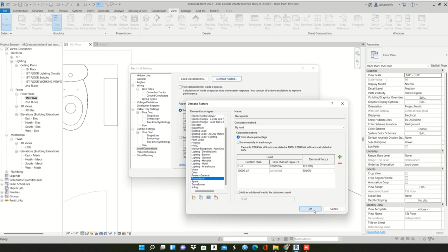Let's assume I'm doing this because we are going to make pizzas, and we're going to use these big machines that consume a lot of energy. I'll hit OK, go back to my panel, and I see my demand factor has changed, it's not 100 anymore, it's 125. So this is multiplying, it's not 1080 anymore, it's...